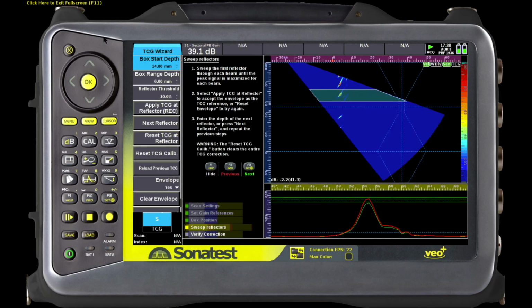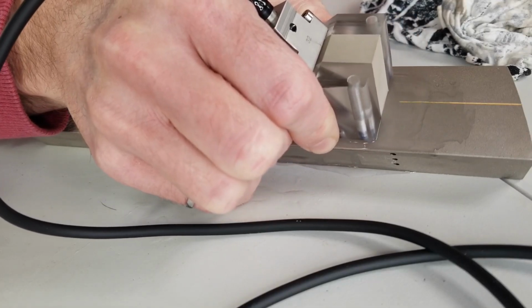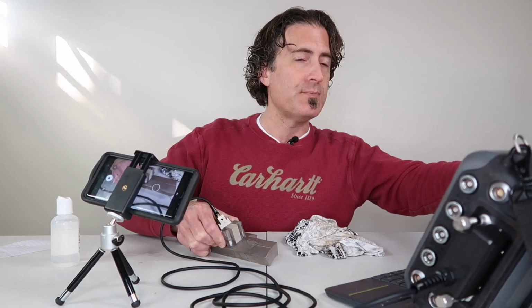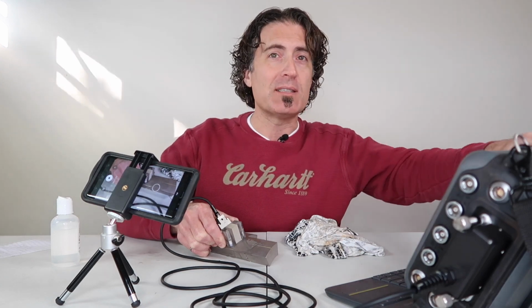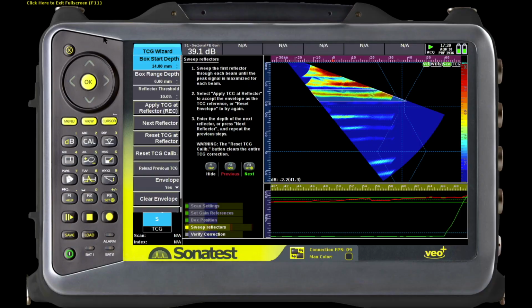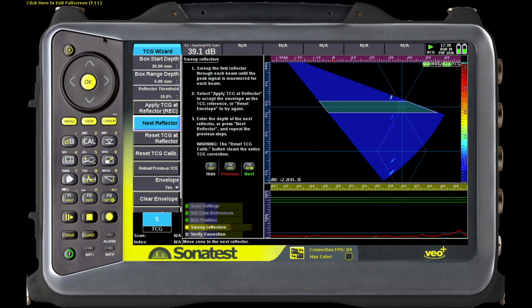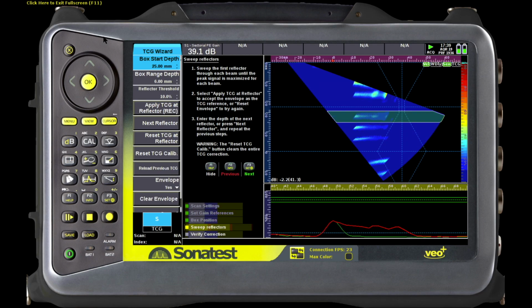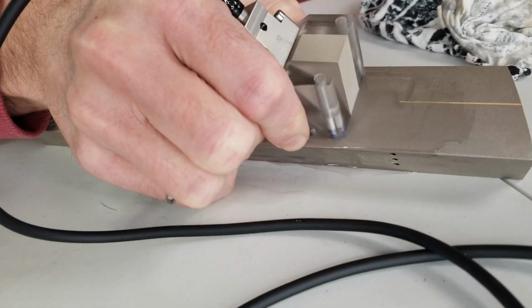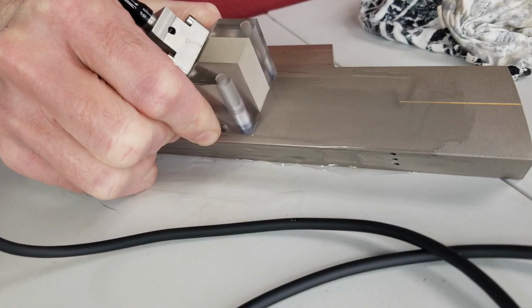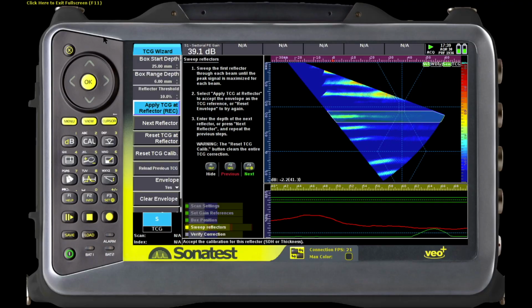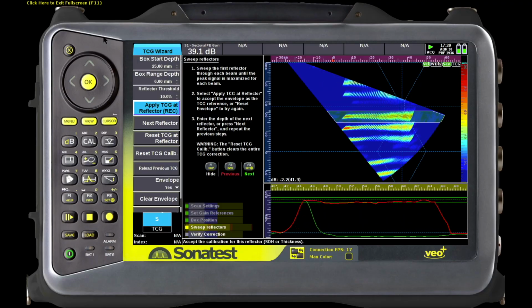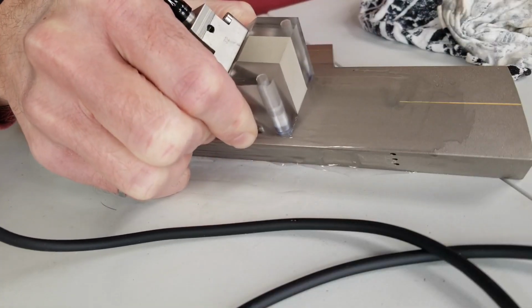So we're going to proceed. And moving the probe back and forth through all of the angles, I'm going to run that. Now, of course, I already did a sensitivity cal at this depth, so that should be right across the screen. That's fine. And then next reflector, I'm going to bump that up a little bit to there. Okay. And then basically rinse and repeat through all of the reflectors that you're going to use for your calibration. Okay. And then double check them when you're done. And what we'll do is we'll just do all of the rest in fast forward.